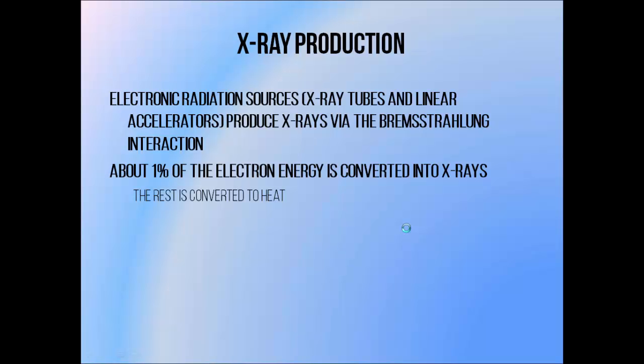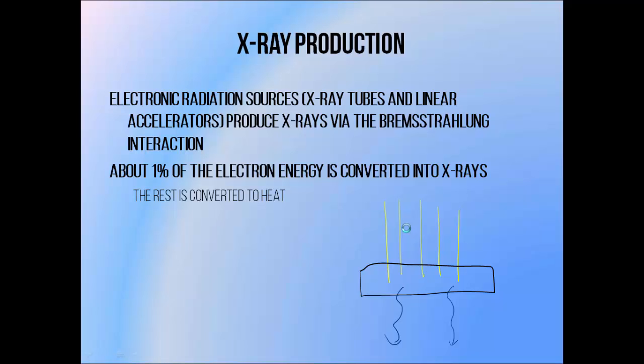Most radiotherapy treatments in the modern age are carried out using photon beams generated electronically. These are usually produced using x-ray tubes, which we're going to be covering in this tutorial, and linear accelerators, which we'll be covering later on. They both use the same method of photon beam production, which is to generate a high energy beam of electrons and slam it into a target material. Inside the target, the electrons undergo the bremsstrahlung interaction, meaning that they lose energy in the form of photons as they interact with nuclei within the target.